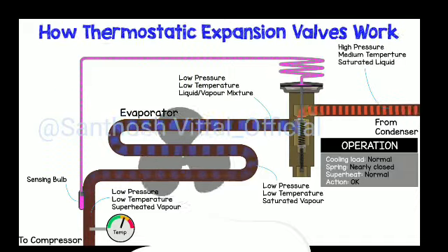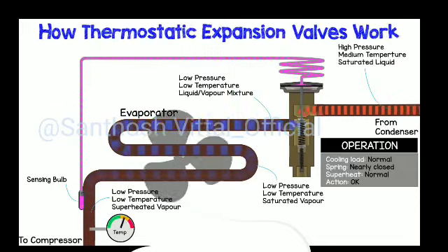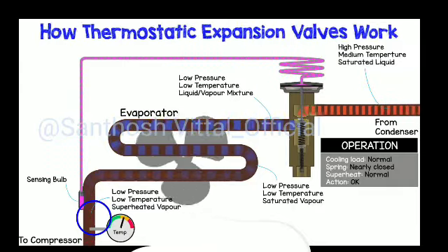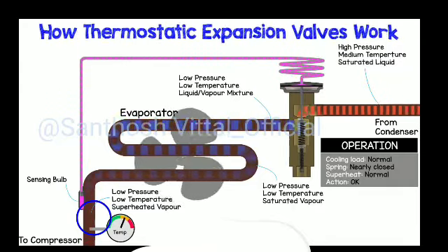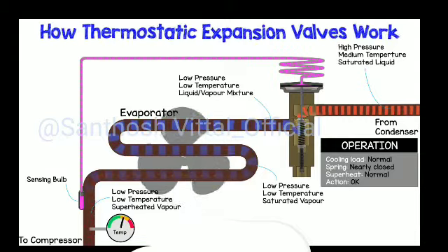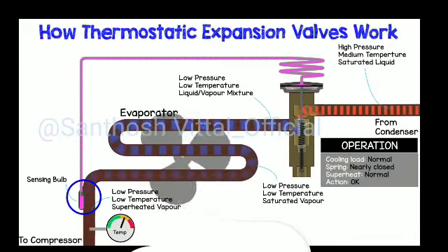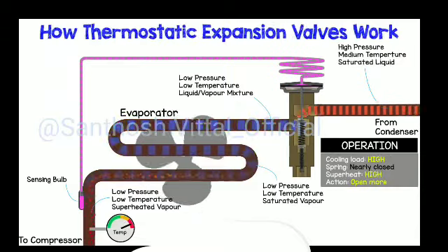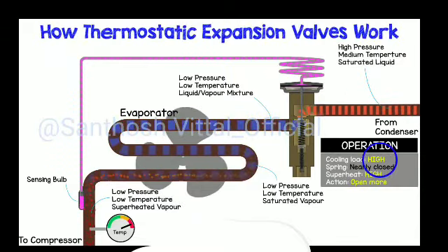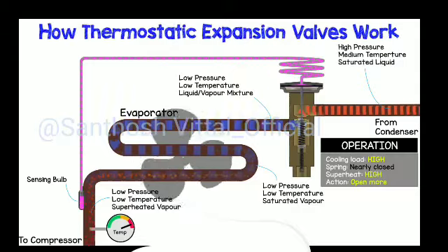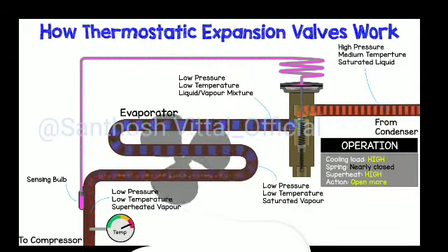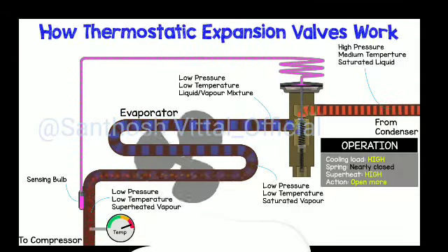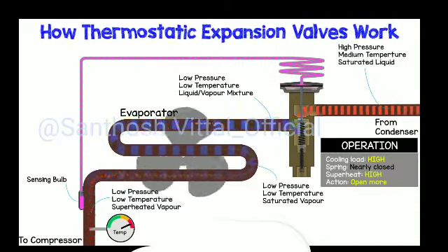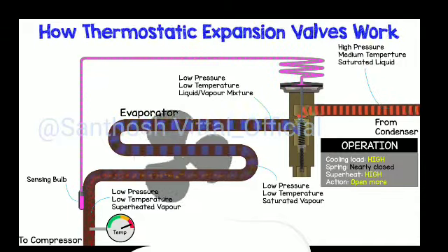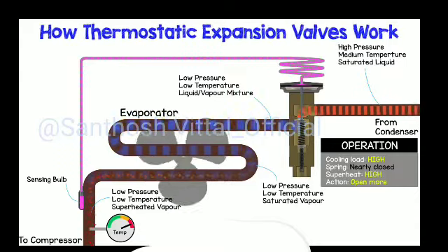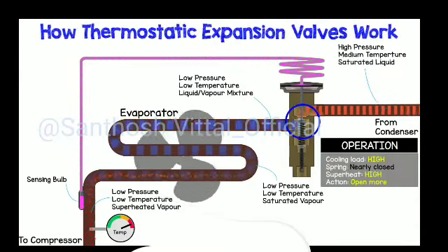The refrigerant will continue to pick up thermal energy, and when it does this after the phase change has occurred, it will then start to increase in temperature. This superheats the refrigerant vapor, and the sensing bulb of the expansion valve is monitoring this temperature to control the refrigerant. So let's have a look at an example. Let's say the cooling load increases. This will cause more refrigerant to evaporate, and the superheat will increase, causing the refrigerant temperature to increase at the evaporator exit. We need to decrease the superheat, and we can do that by allowing more refrigerant to flow into the evaporator. So the pin will need to open more to let the refrigerant pass through.